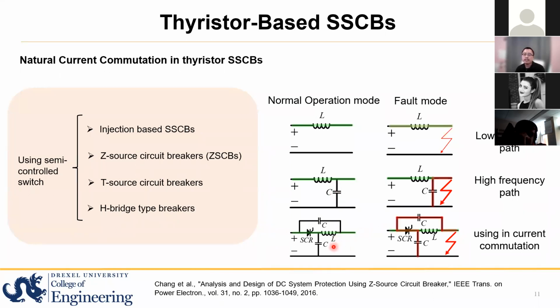And this circuit breaker is actually utilizing this high frequency path to protect the circuit, and specifically it is using the discharge of this capacitor to turn off the thyristors. You could see this is a typical Z-source circuit breaker. It has two capacitors, two Cs here, connected through this thyristor. Normally the thyristor is turned on, but when we have a fault, this capacitor will discharge through this thyristor, and then we could see it has a negative direction current to cancel the positive current in the DC system. If this negative current exceeds the positive current, this thyristor will be turned off, and we call this process the natural current commutation.